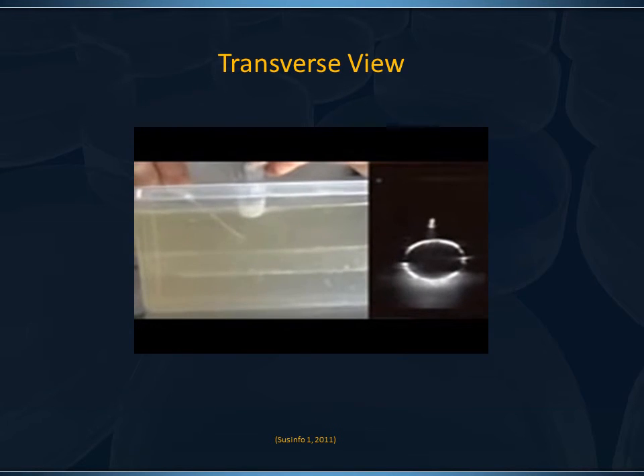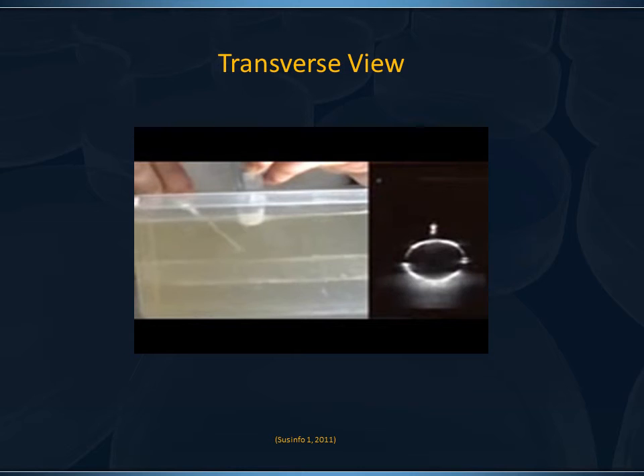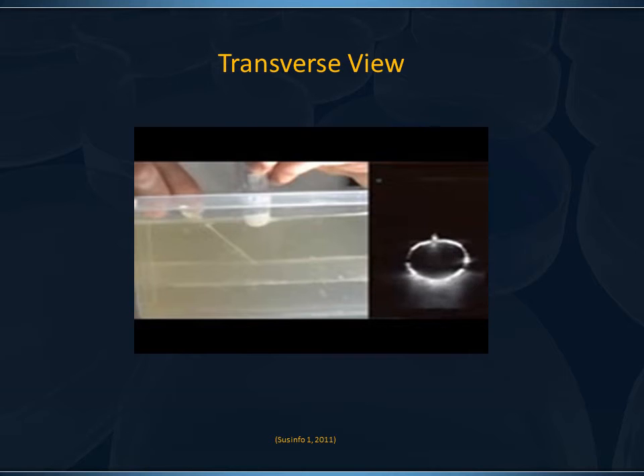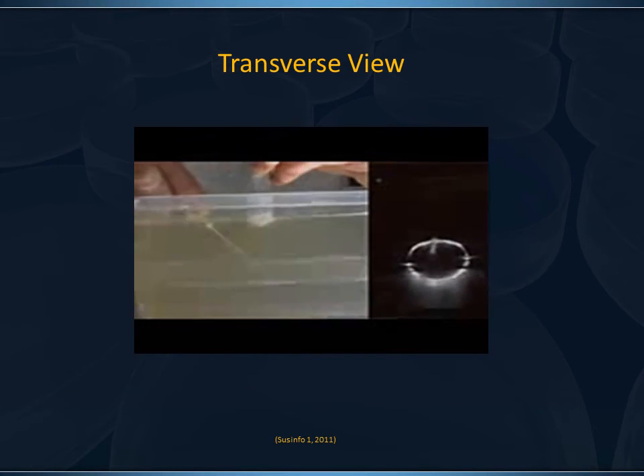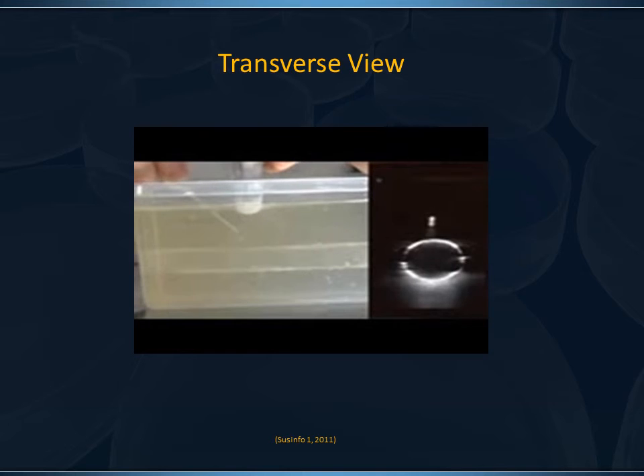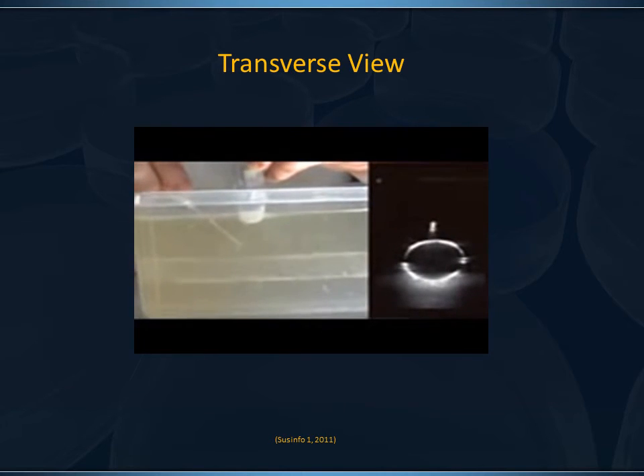Now, what's important in this view, which is known as the transverse view, the probe is held perpendicular to the needle cannula. And what you're seeing is the front or the back view. You're seeing a circle, and that silver dot or slash on top of the circle is the needle cannula. The other thing that I want you to notice is how the transducer, the probe, is moving from left to right. That's being done because the user wants to make sure the probe is right at the tip of the cannula. You always want to know where the tip of the cannula is because you don't want to perforate the entire blood vessel.